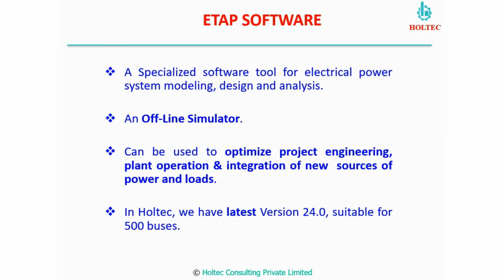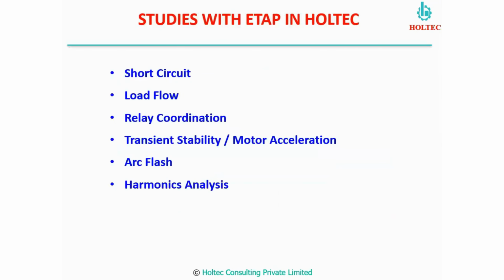In Holtec, we have the latest version of ETAP software, which is suitable to handle 500 buses. Now, what are the studies which can be offered by Holtec on ETAP? We offer almost every sort of study which is required for a power distribution system: short circuit, load flow, relay coordination, transient stability, motor acceleration, arc flash, harmonics. We have all modules available for these studies.